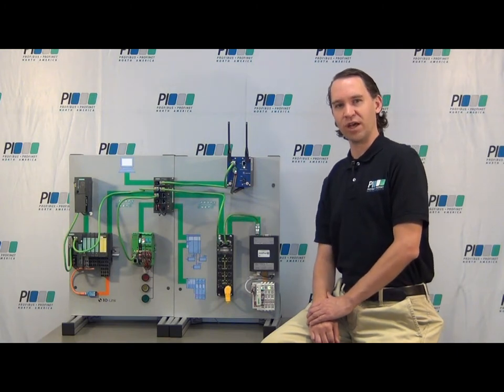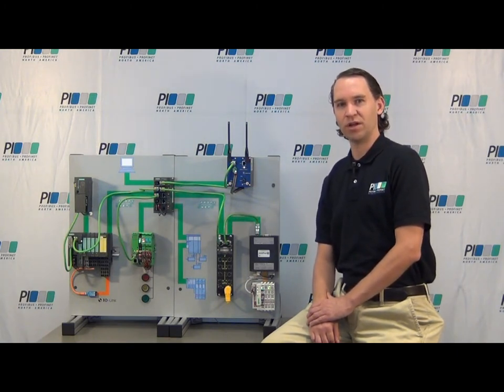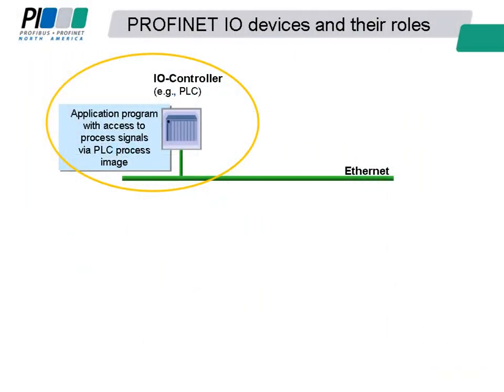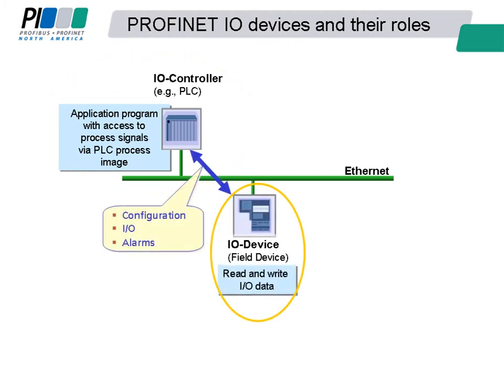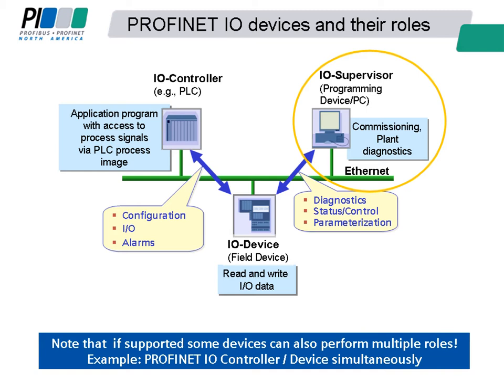When discussing Profinet, there are three main device roles depending on the device's function. The Profinet I.O. controller communicates to the I.O. devices as the controller of those devices, writes the process outputs, and has the main user program. Profinet I.O. devices send the process signals to the controller, such as inputs or diagnostic messages. I.O. supervisors can obtain status and control information from the devices and parameterize the system. Note that if supported, some devices can also perform multiple roles — for example, a Profinet I.O. controller and device simultaneously.